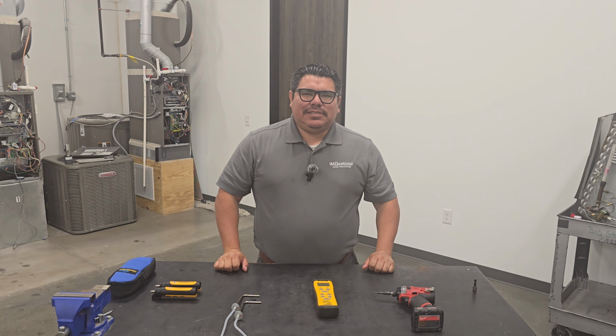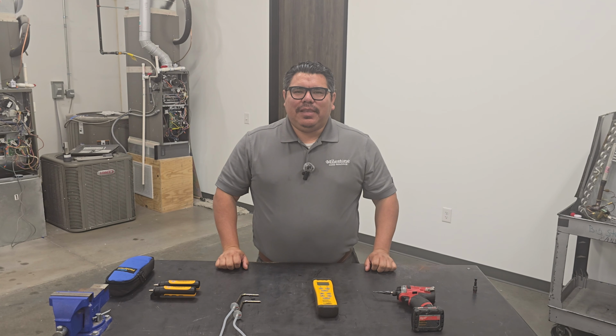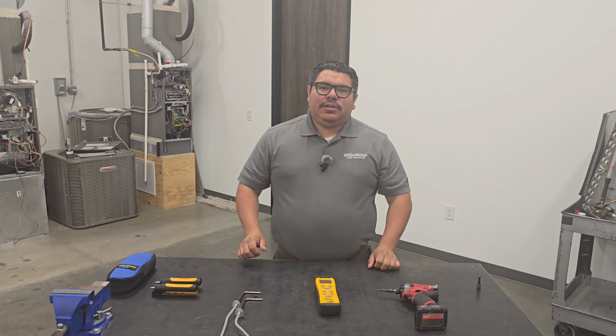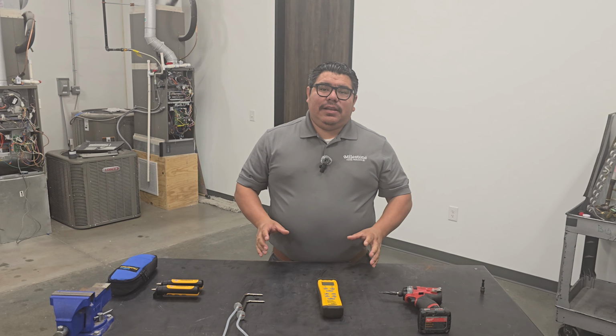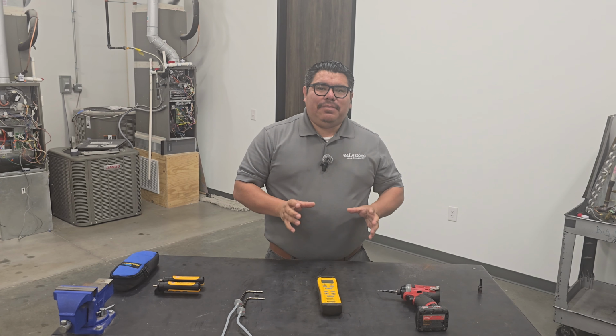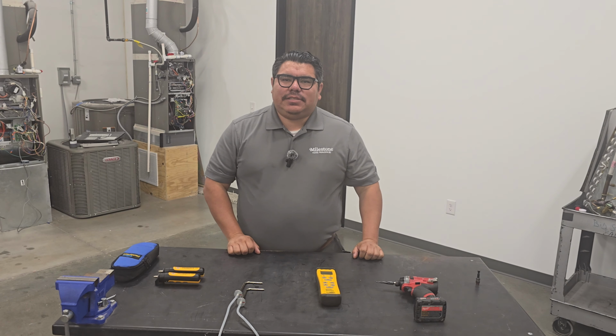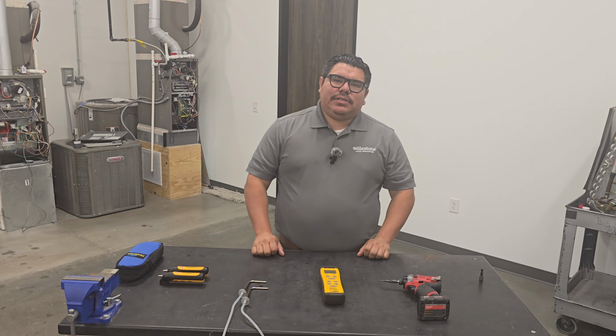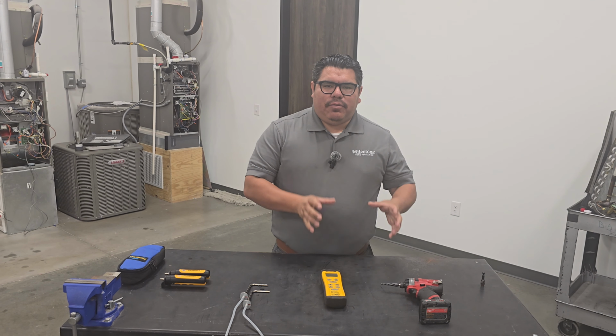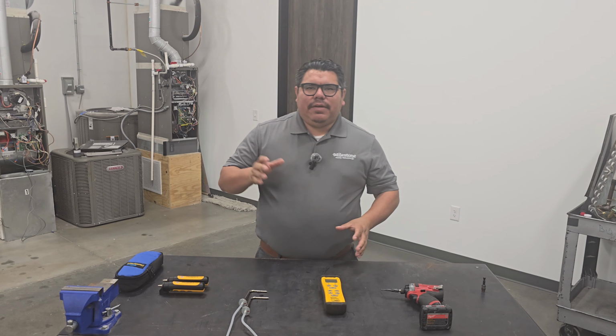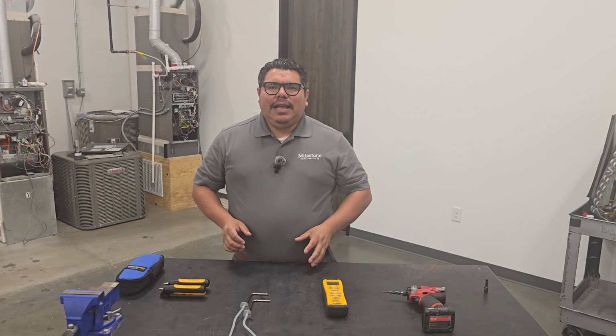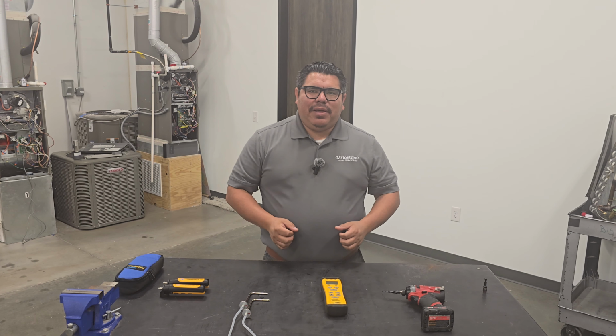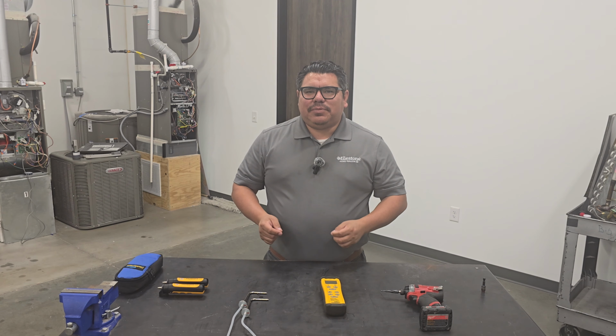Back to callback solutions. Today we're going to be looking at airflow. Now, while a good technician is going to look at the return and supply and calculate how much CFM they have, a great technician is going to look at static pressure. The reason you want to look at static pressure is that you're going to know that you have the proper amount of airflow, which means you'll be able to check the charge, and that means you're going to be pulling the correct amount of humidity, making the system as efficient as possible.